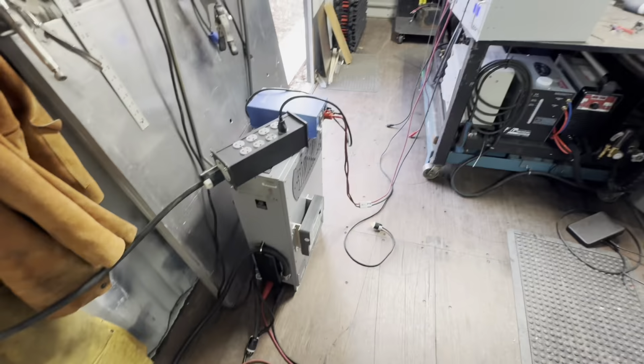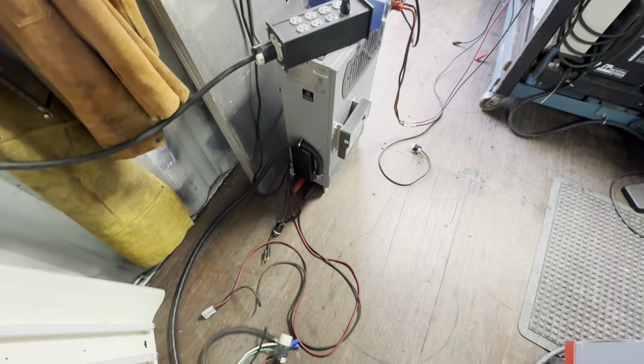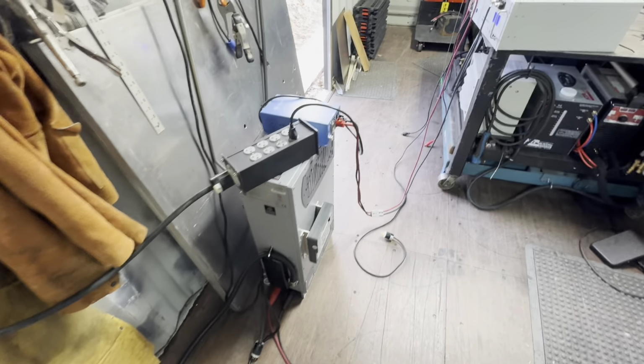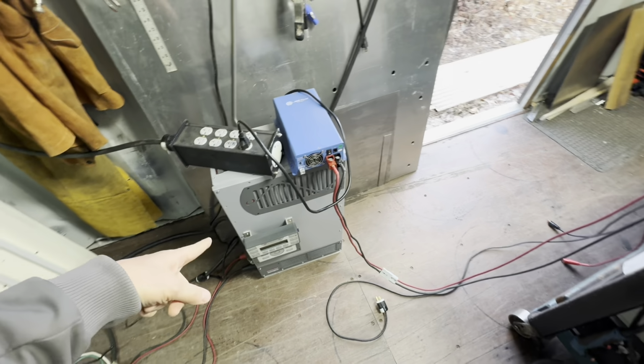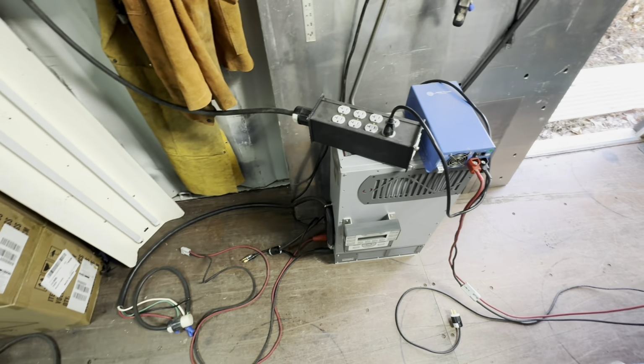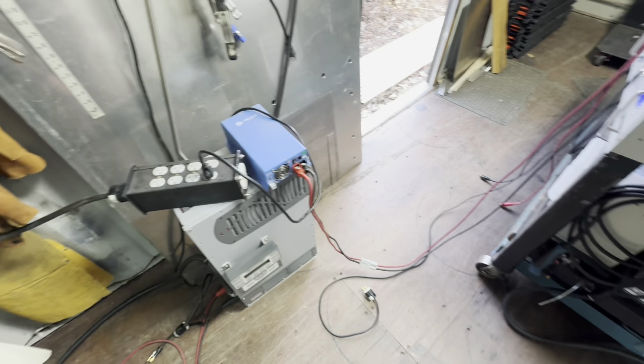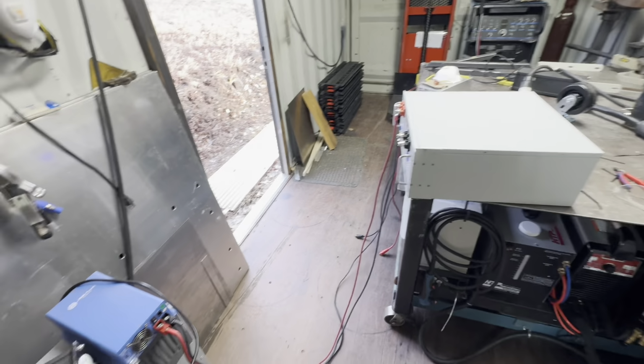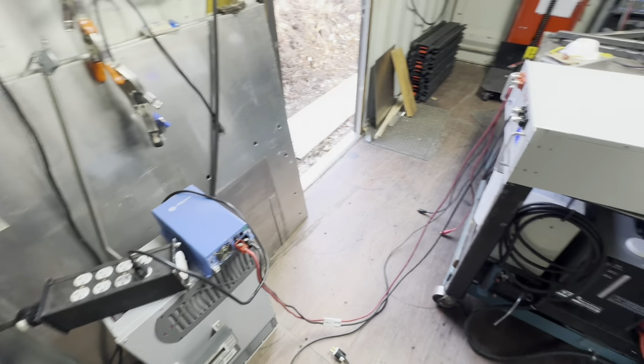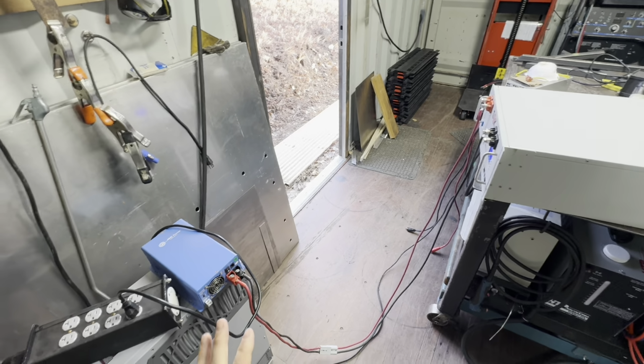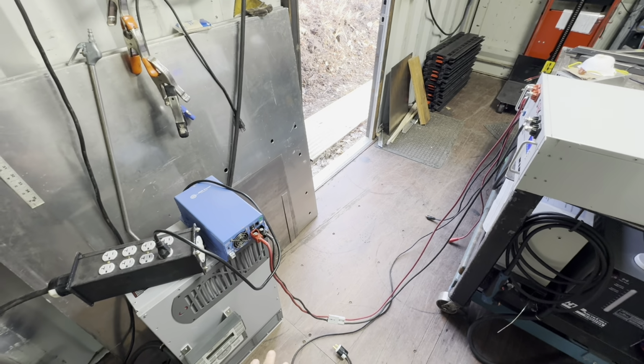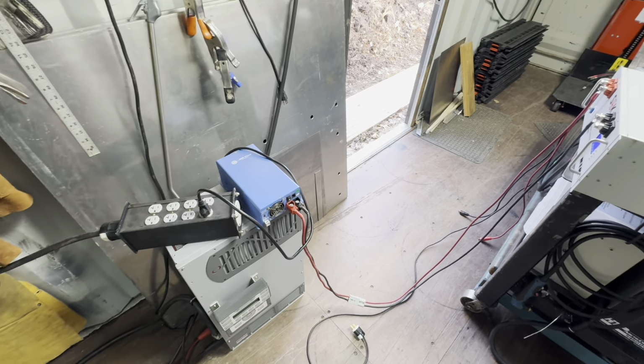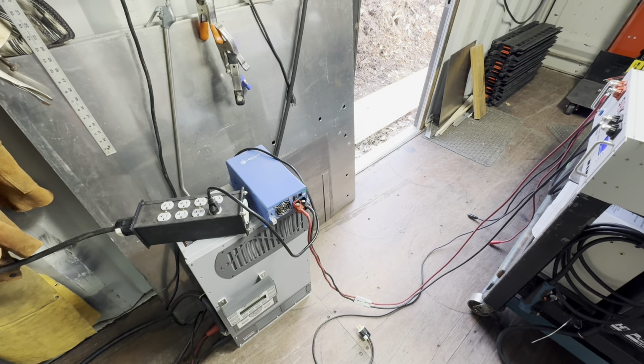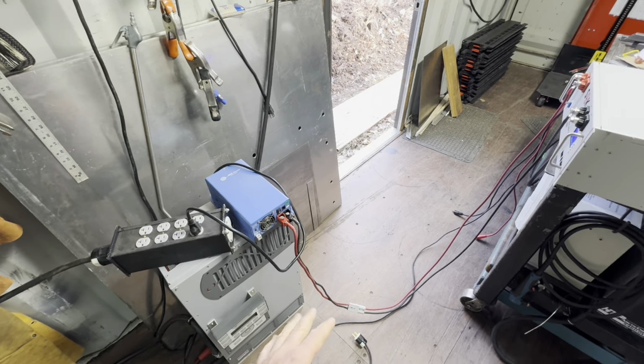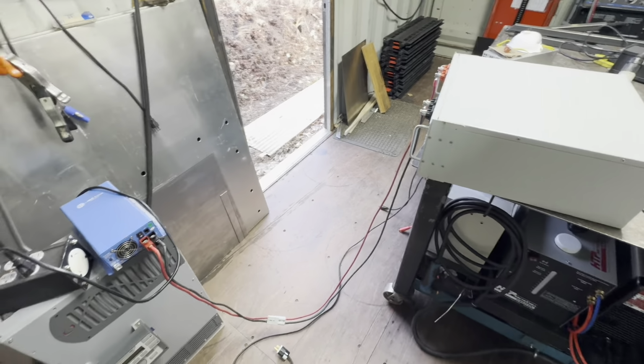Thanks. Okay, it looks like this is about the end of the battery story. So I ran this inverter down to the battery disconnect voltage, and I ran it with a string of Christmas lights so that I would drain the battery as low as possible without the voltage sag cutting it off before it's totally dead.